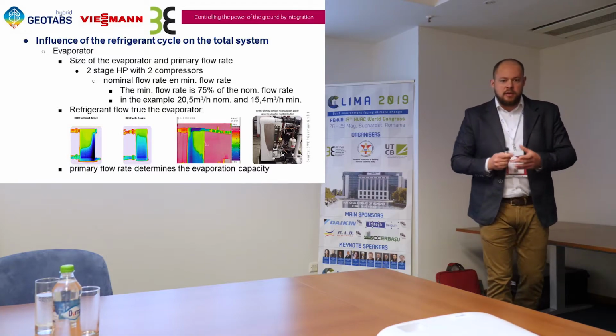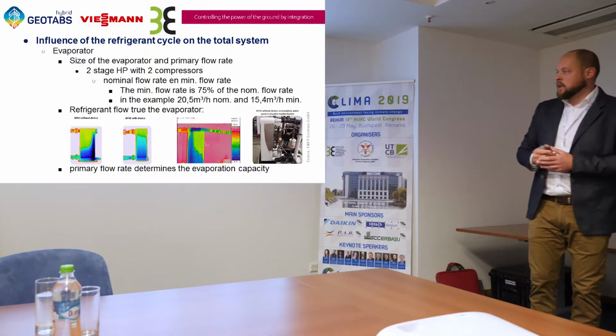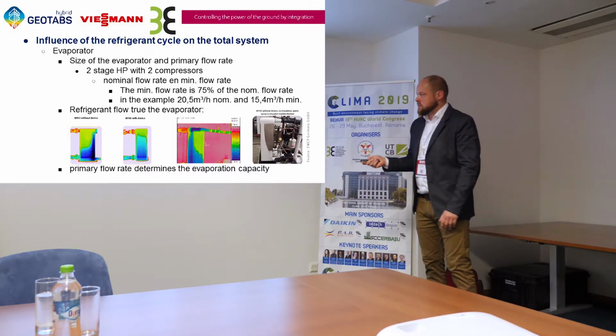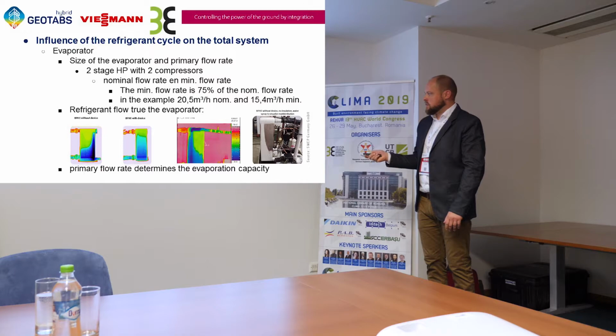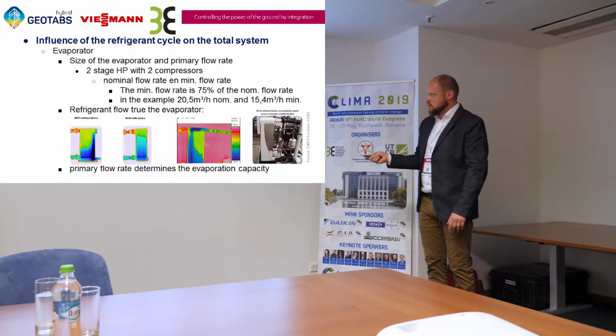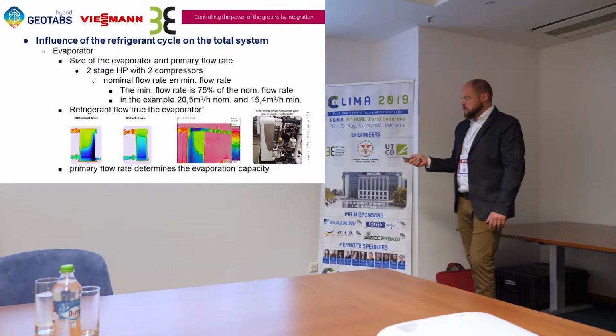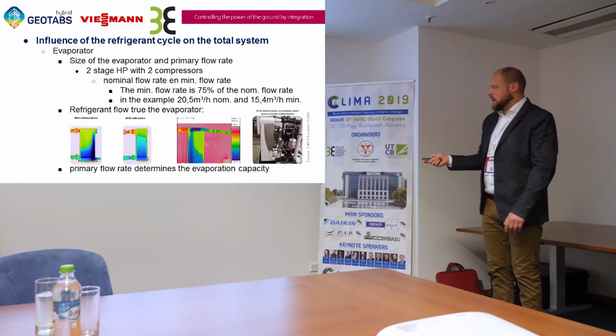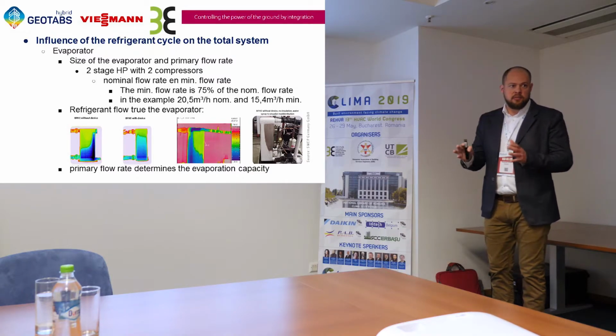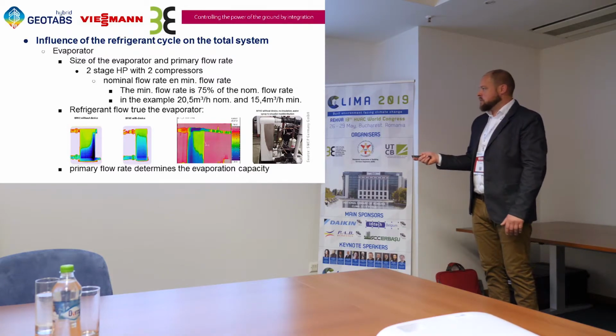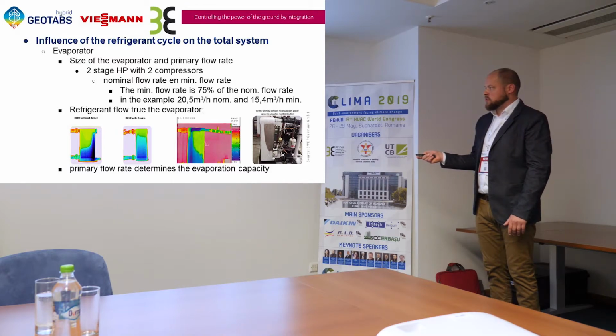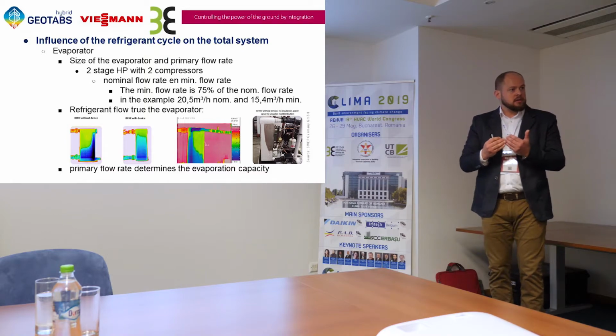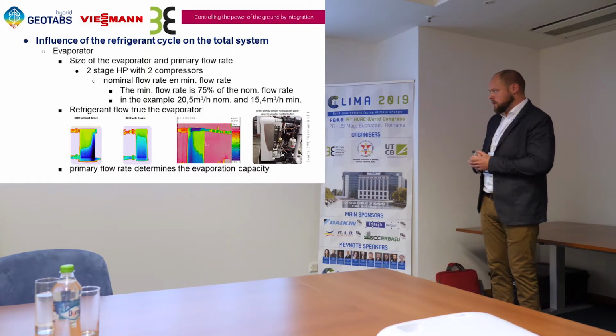What can happen if the flow rate through the evaporator is too low? Then we can have that the refrigerant is not evaporated completely. As you can see in this thermal picture, the refrigerant is going through the evaporator in this direction, and the flow of glycol mixture is going in this direction. And what do you see? That in this case, the flow rate was too low, and we have liquid refrigerant going to the compressor. And that has to be avoided at all costs. So what will happen here? The electronic expansion valve will detect the low temperature here, and it will close off. So the power that is obtained from the source will be much less.